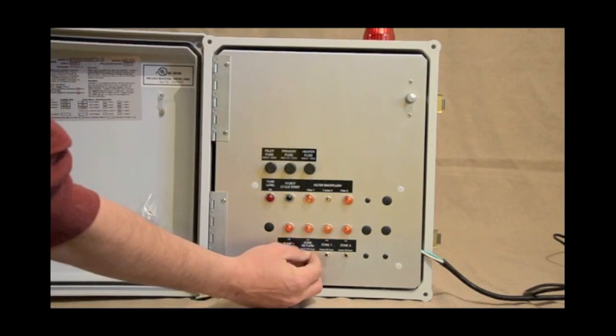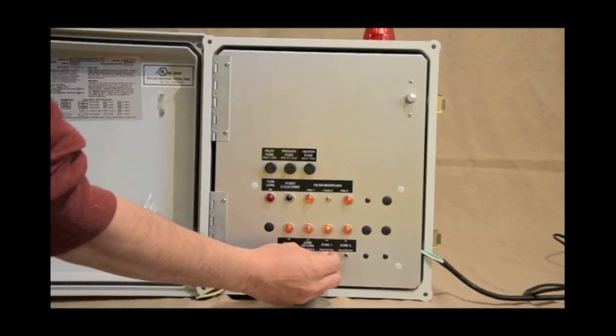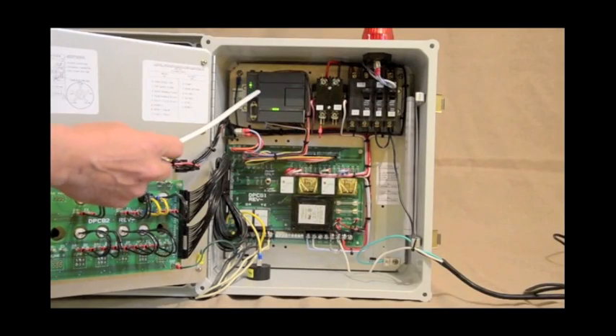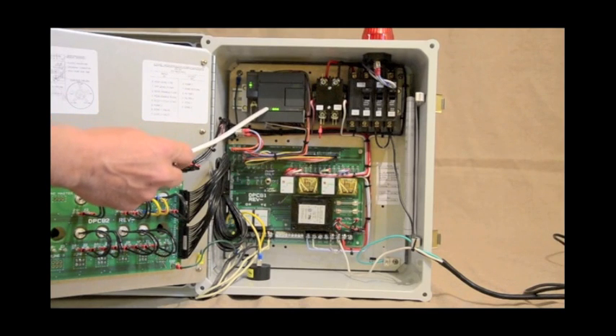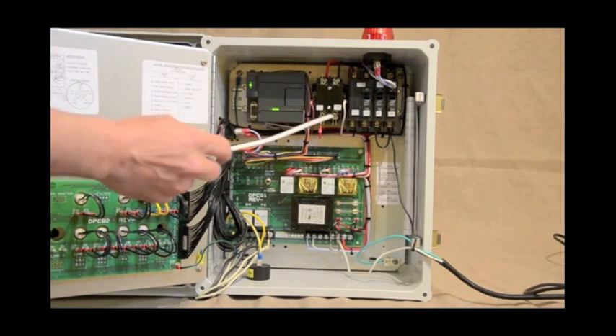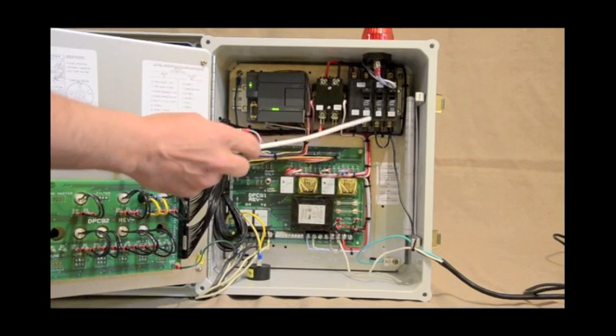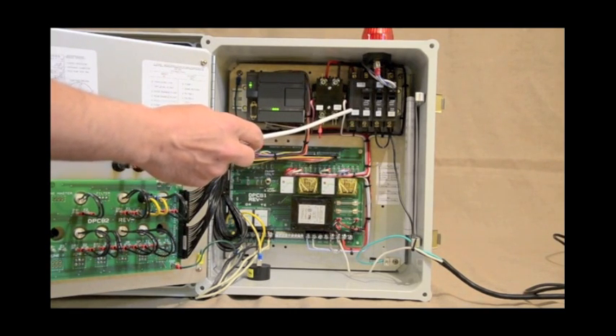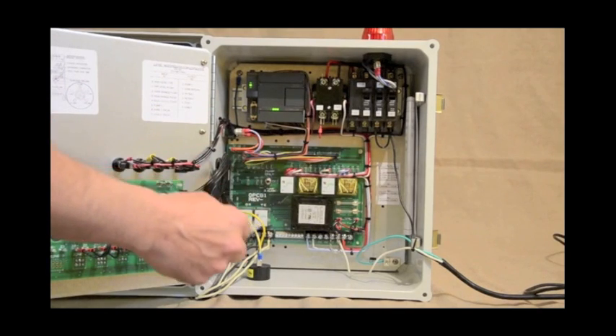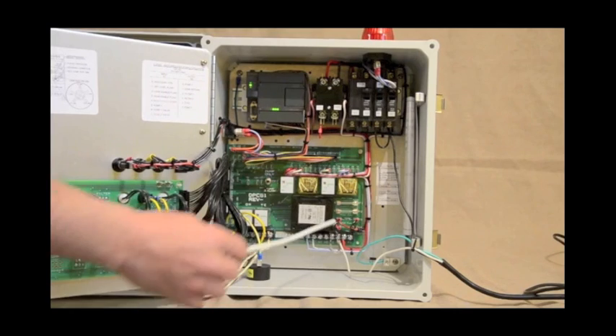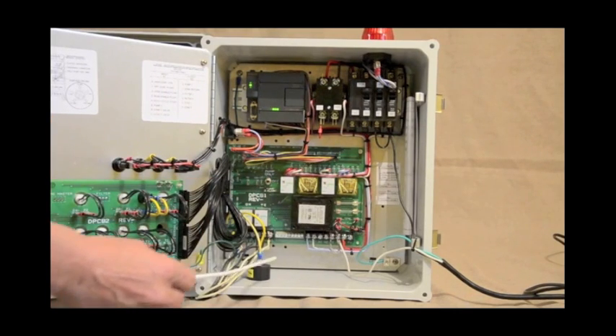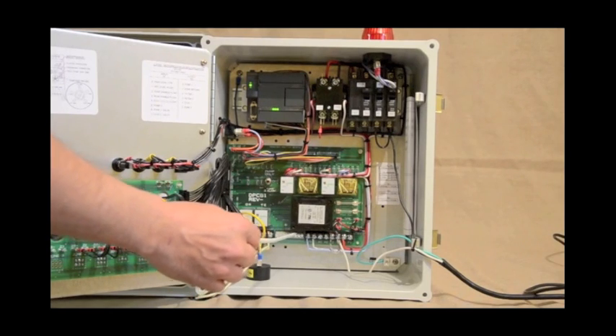The lights operate both in hand and in automatic for each of the solenoids. Inside the control panel you'll find a processor with its indicator lights, motor contactor, circuit breakers, and the main backplate circuit card. This card holds the fuses, transformer relays, and the connection to the hydraulic unit.